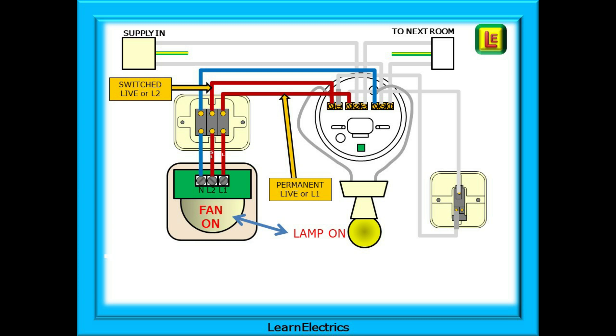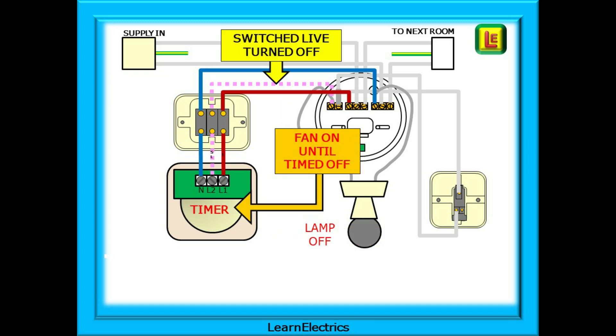Correctly connected, when the lamp is on the fan will be on. If we turn the lamp off, the voltage on the switch live will drop to zero — shown here by changing the L2 cable from solid brown to a dotted line, indicating no voltage. The fan will now continue to operate until the timer reaches its preset time and it too turns off.